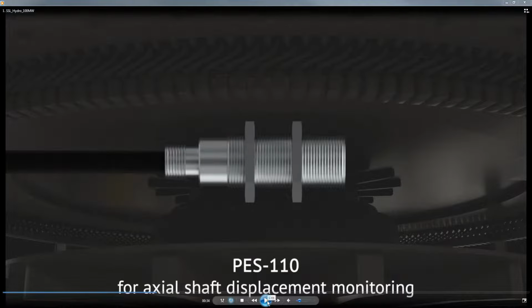Now, in some cases, it's important to be able to monitor the axial displacement of the unit. I'll show you an example. We have a small video on that, and in some cases it's important to measure the axial displacement to protect the thrust guide bearing. In some cases, you have thrust guide bearing wipeouts, and people wonder why that is, and sometimes that little probe will tell you exactly what the problem is. So we'll take a look at that as well.